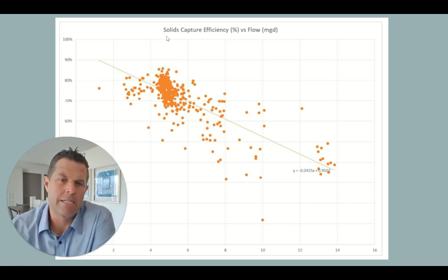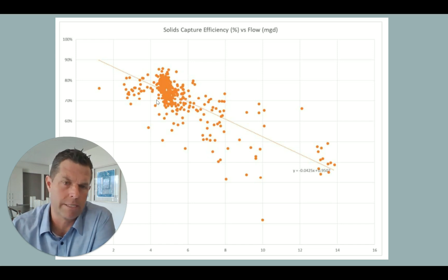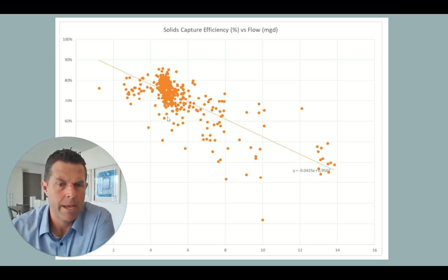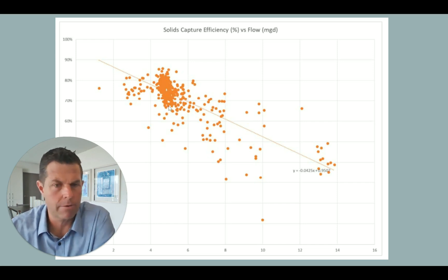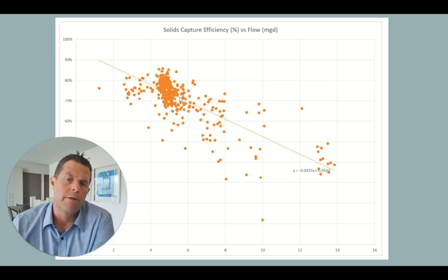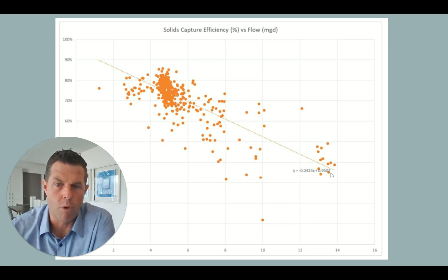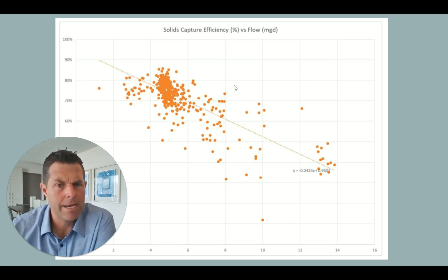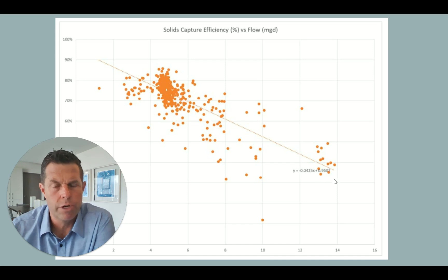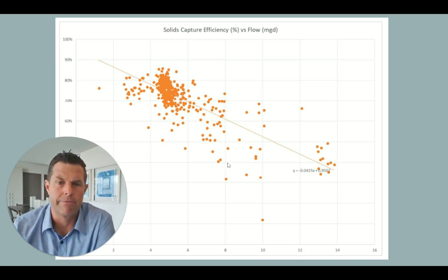There are a lot of lessons to be learned out of this data. Down at the 5 MGD flow rate, the data is really tightly bunched and the performance is very good — solid capture efficiencies between 70 and 80 percent. A lot of times when I talk to plant managers and ask how things are performing, they say great, and this is the set of data they're talking about. But what happens in a lot of clarifiers is that as the hydraulic loading increases, performance really deteriorates. This data really shows what the plant manager was describing — that the performance of this clarifier really deteriorates as flows increase.